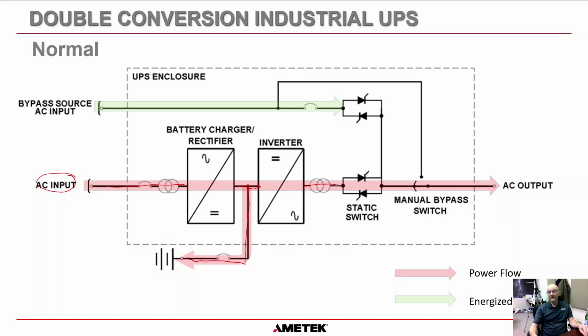That goes into, for an industrial UPS, an isolation transformer, and then that goes into the static switch, and this static switch will be on. We call this the inverter static switch, and this one up here is the bypass static switch. So the inverter static switch is on and the bypass static switch is off. And then that power flows through the manual bypass switch, which is internal to the UPS, and out to the load circuits. So that is the basic normal operation of a double conversion UPS. Okay, let me erase that.